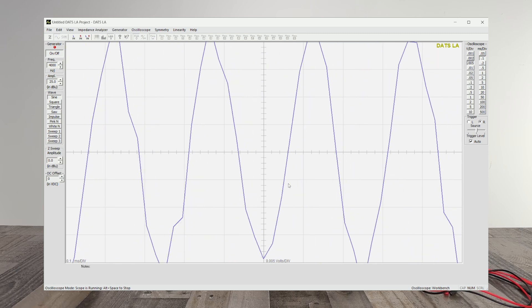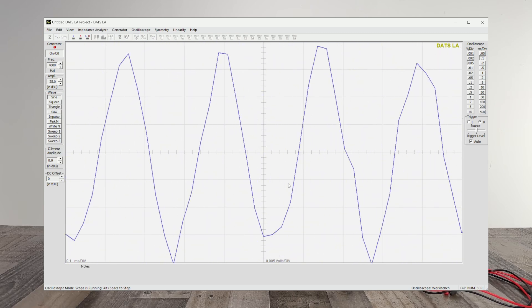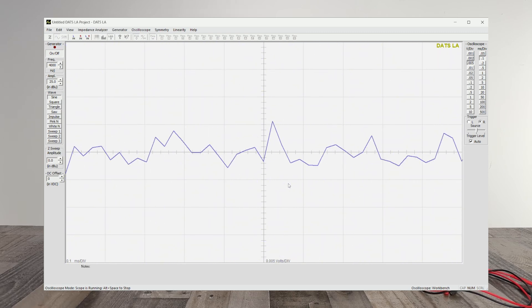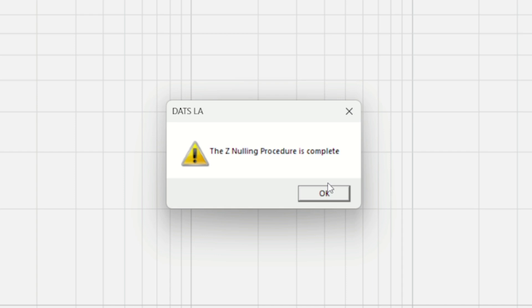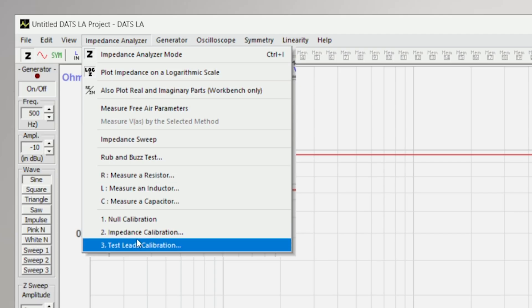And then once it's completed, there we go. The nulling procedure is complete. You say OK, we go to impedance analyzer again, go down to impedance calibration.